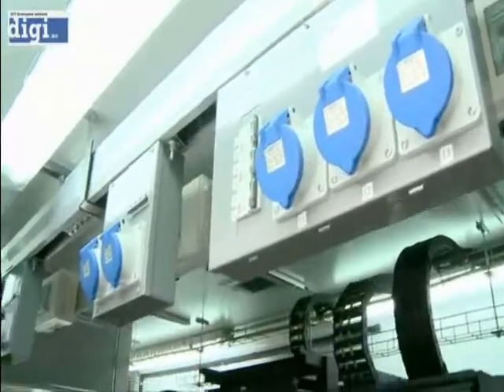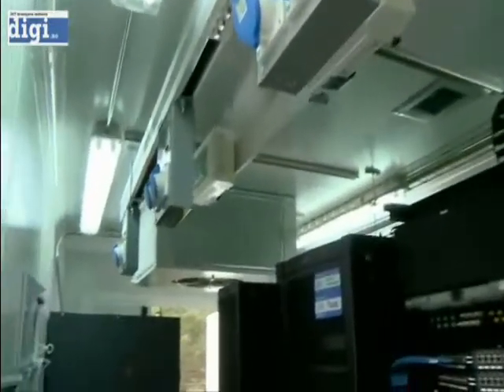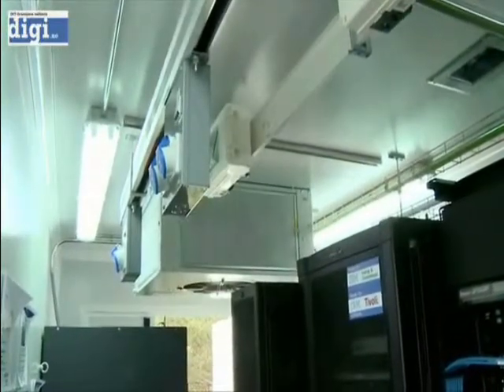What you need when you put a container in, there are 3 different interfaces you would need. One is just raw electric power, which we bring in, a water source, very minimal water for the humidifier, and then basically a network connection. And your network connection is going to be a communication to the outside world. So those 3 things that you bring into a container, that's all we need. So we can install anywhere in the world as long as we have those 3 sources.